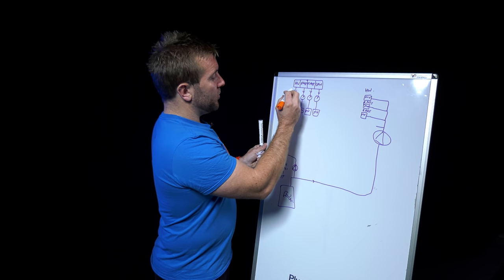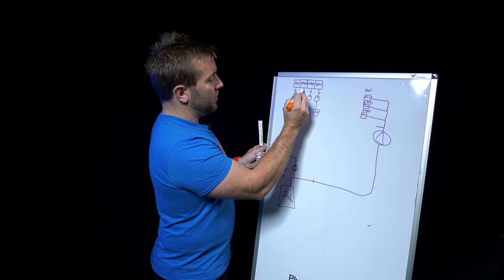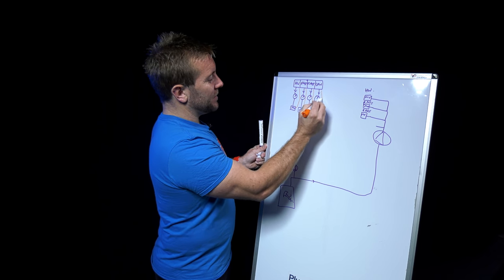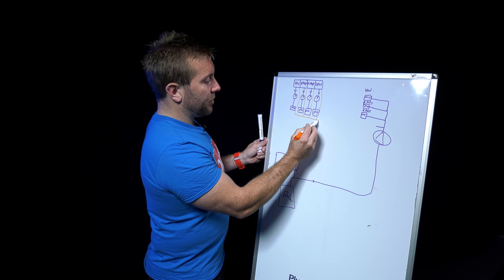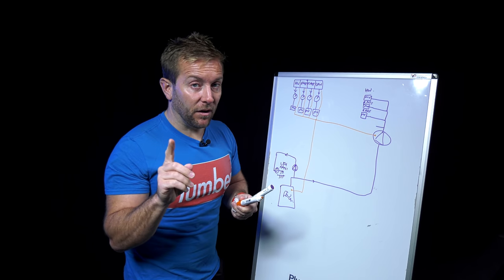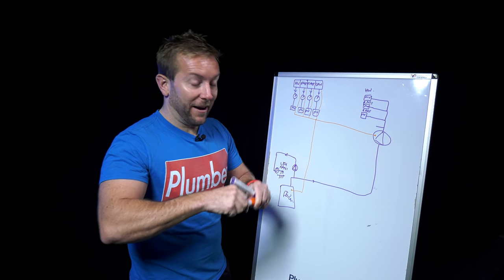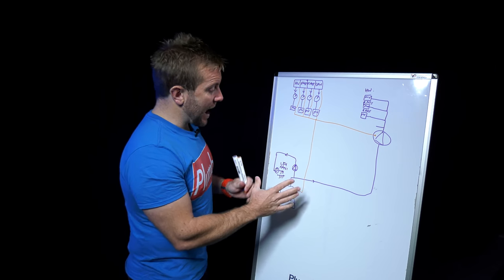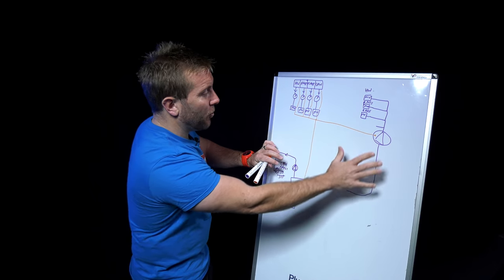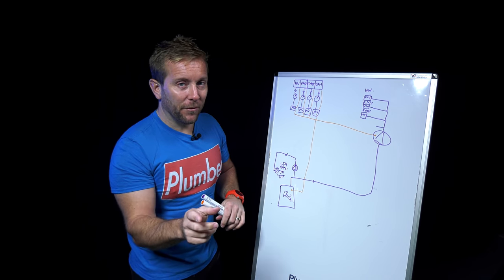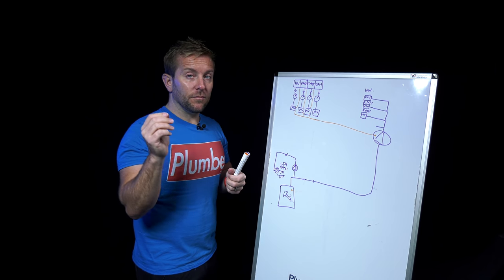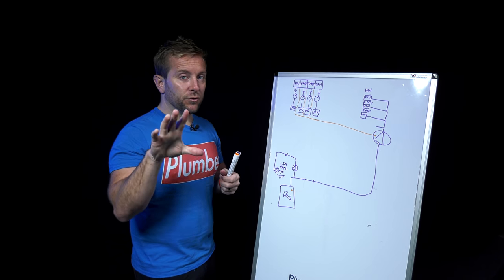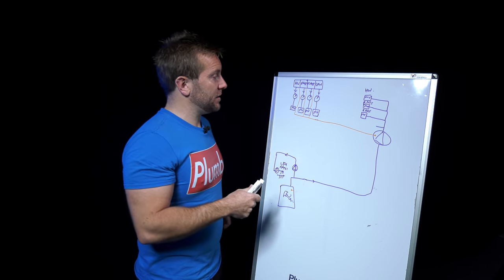We've effectively got four switches coming out of our time clock. We've got one for hot water, one for rads, another one for rads, and one for our underfloor heating. We have a thermostat on the hot water, on the radiators upstairs, on the radiators downstairs, and on the underfloor heating. We also know that every one of these has a motorised valve, and we also know as well that that's where these lives stop. We also know that we've got a switch live that switches when that's opened. When any of those are opened, they will send a live supply to this pump and to the boiler. They share that live supply.